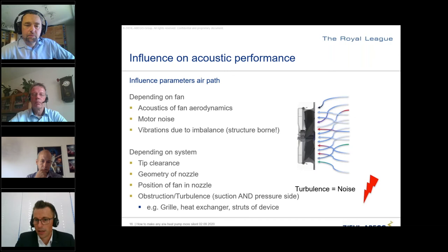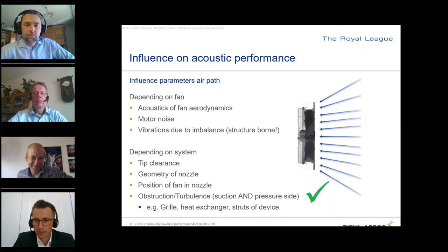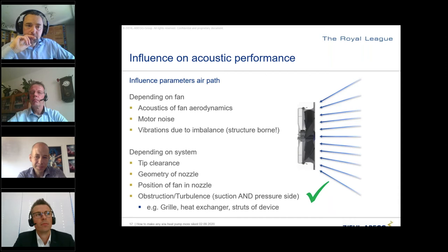The perfect situation would be if the air comes in like that. There are additional parts for fans on the market as well, which straighten the flow at the inlet of the fan. But you have to take into consideration that this is another place where icing can occur, and after all, it's just a patch to straighten the flow. If you had just built the unit a little bit bigger, or avoided some turbulences in the unit, this would make for better performance than putting some flow straightener in front of the fan.